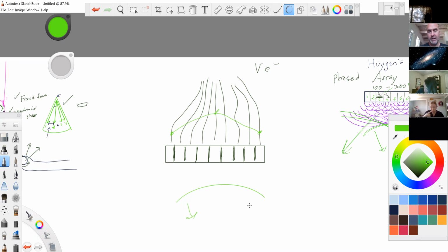And of course, what we've done here is focused. That was a focus voltage. We told the machine, bring the focus up to here. So the machine said, okay, I'm going to stimulate these outer ones first, and then 5 microseconds later, I'm going to stimulate the last ones. So there's a progression of voltages.